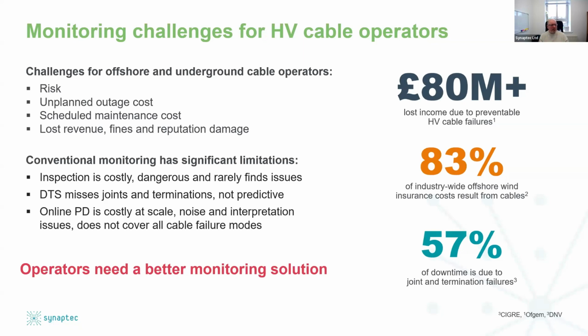And often that happens, particularly on the generation side, with large inverters, that online PD signals are completely overwhelmed by the high frequency electrical noise generated by things like solar panels and wind turbine generators, such that you can't really detect it, and it's not absolutely clear if this is a problem or not. And so the noise factor, the attenuation, the interpretation issues make it quite a subjective and expensive thing to deploy. What operators asked us for was something more simple, a traffic light system that's either a red light or a green light. I'm okay to keep going, or I need to stop and there's a problem. So the idea here is to give the operator much higher confidence that there's going to be a problem to justify an intervention to go and check.